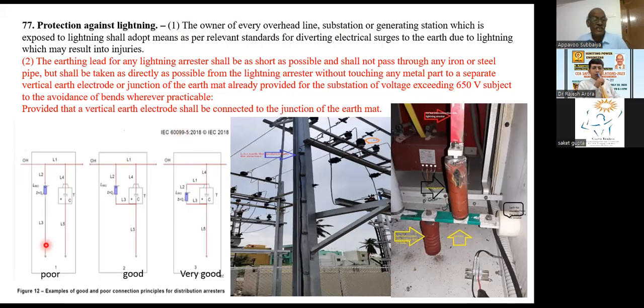This is good. This is poor because, for example, if you lay the lightning arrestor with a separate earthing and the transformer with a separate earthing, this is a poor arrangement. They have shown it with the figure. And if you connect it like this, it's good. If you have avoided this length of conductor and minimized the loop, here you can see this is the loop. Here there is no loop at all. Here this is a big loop. Here this is a small loop, where during the lightning surge the L di by dt will be very less. Here that will be very high.